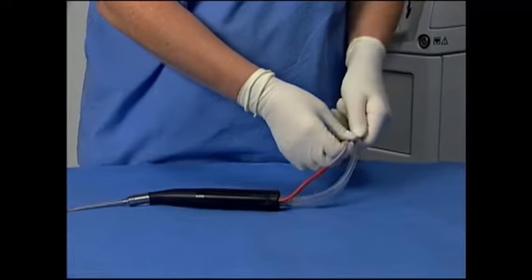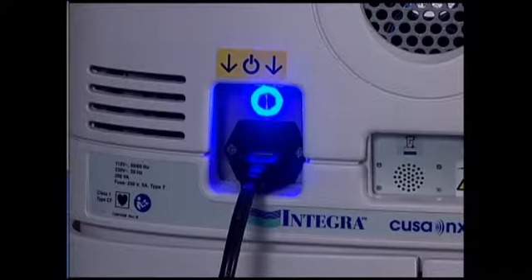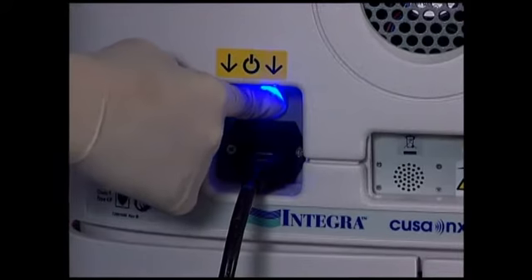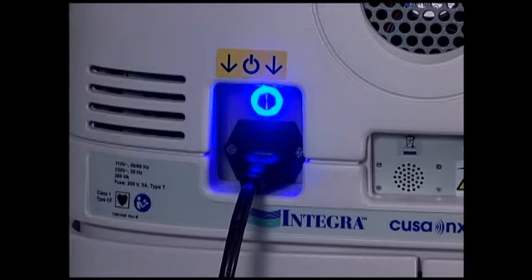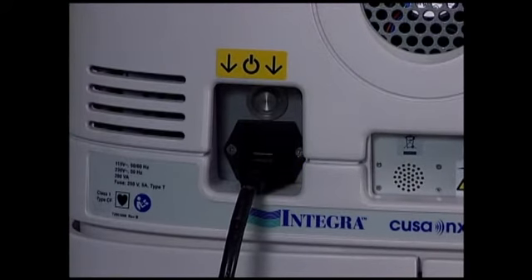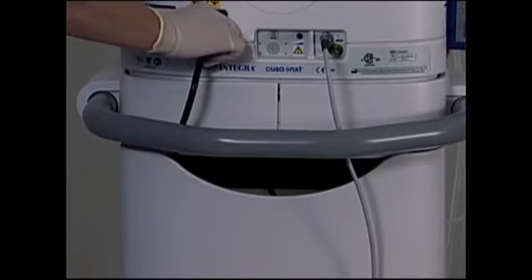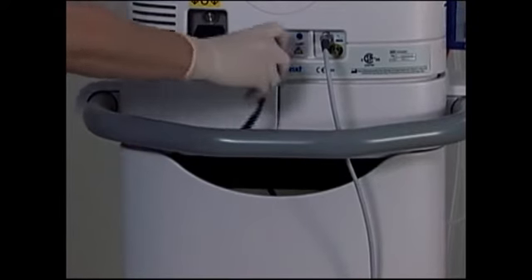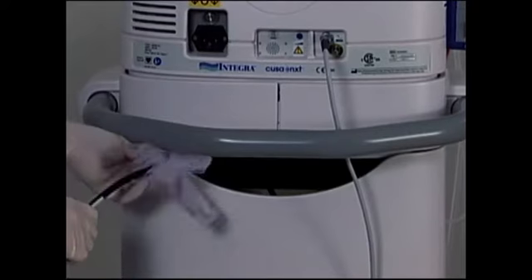After the procedure, flush the handpiece by aspirating at least 100 milliliters of saline. Then remove the hose clips from the handpiece cable. Turn off the power switch on the rear of the console. Remove the power cord by pulling on the metal housing. Wipe it clean and store it in the rear of the service module.